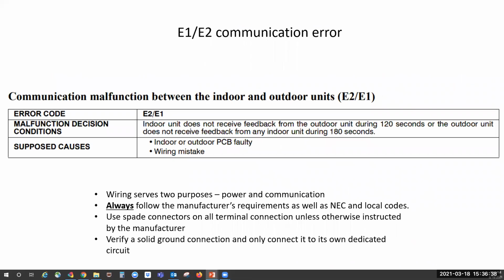E1 error, communication. If this happens upon startup of a multi-zone system, you want to double check and verify your piping. There are several ways to do this. You can unhook all the heads but A electrically, and turn it on. If it runs, refrigerant is going through the proper pipe and that one's good, and you just hook up the second one and keep going down the line.